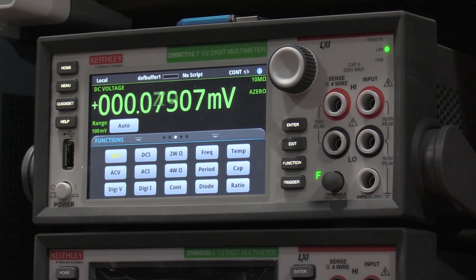I thought I would do a presentation on what you get and what to expect when you send a moderately high-end piece of test equipment out to the manufacturer for alignment or calibration. In this case I sent it out for calibration, which did not include an alignment at all. A lot of the historic videos on the channel are alignment procedures, not calibration procedures. I'm doing the adjustments to tighten up the scope specs and bring it in as close as I can. With a calibration, if it meets specifications — especially published specifications — they won't adjust anything on it. They'll just say, yep, meets specifications, and send it back.